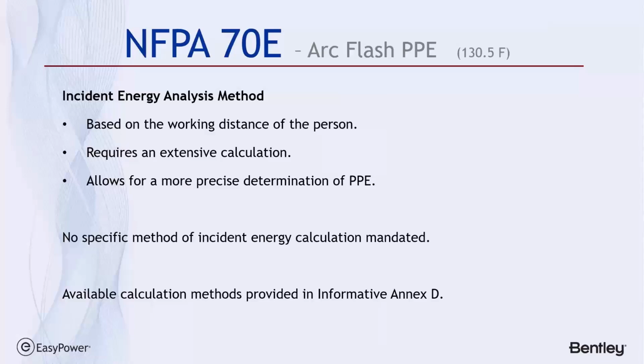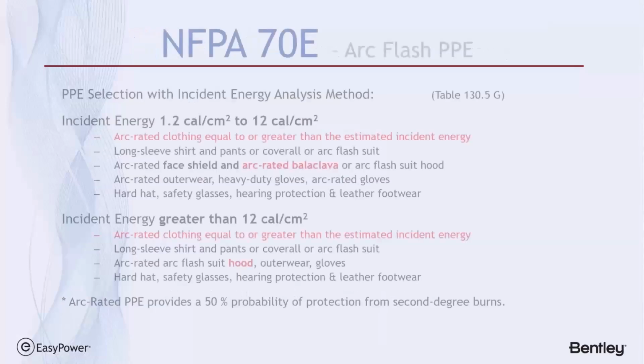The reason for it is that it gives us a more, quote unquote, precise determination of PPE. I use quotes because in all the literature, standards, and test results that IEEE reported, they use the term estimated results because there's a lot of variability in the data that was taken during testing. It's important to note that there's no specific method of incident energy analysis mandated in NFPA 70E, but there's a list in Informative Annex D that talks about other methods, other scopes, and DC, which is not covered by IEEE 1584.